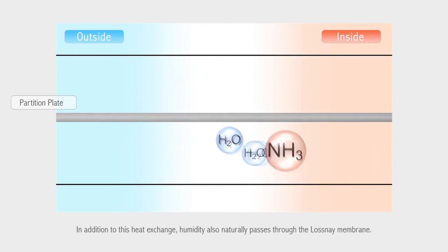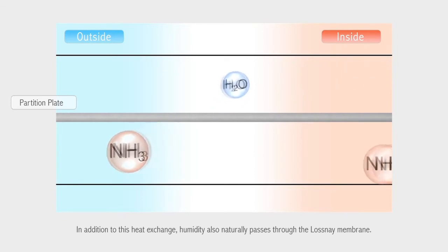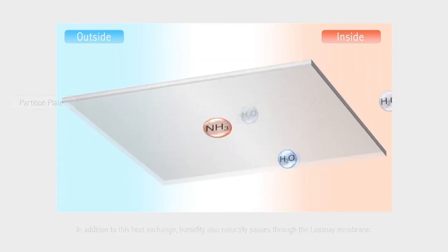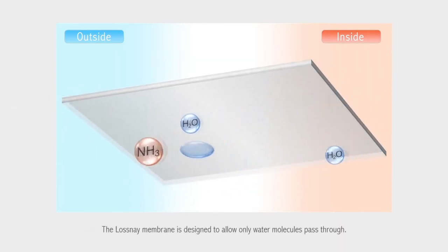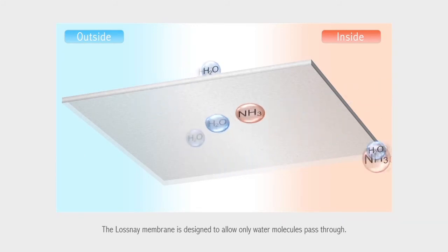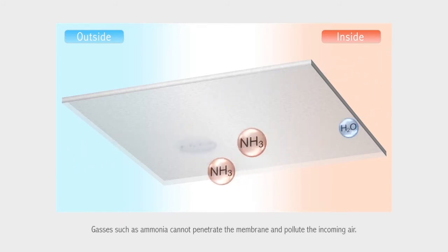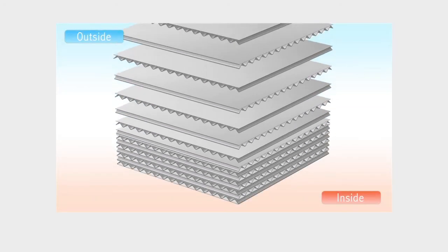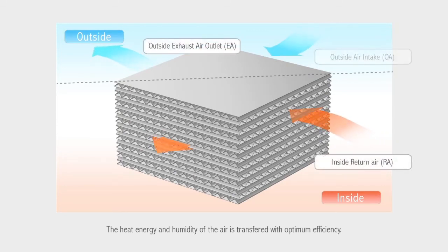In addition to this heat exchange, humidity also naturally passes through the Lossnay membrane. The Lossnay membrane is designed to allow only water molecules to pass through. Gases such as ammonia cannot penetrate the membrane and pollute the incoming air. The heat energy and humidity of the air is transferred with optimum efficiency.